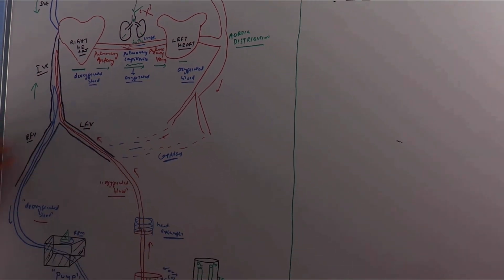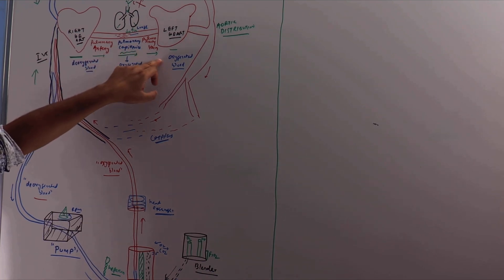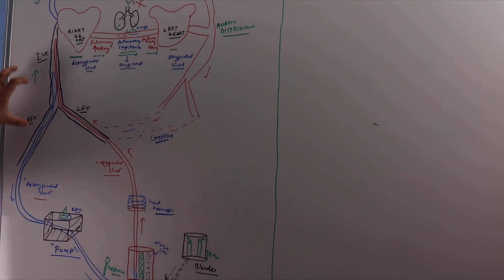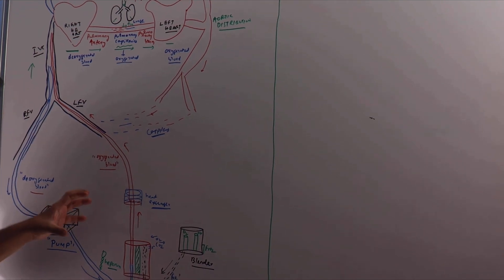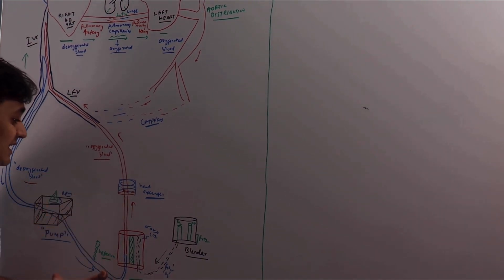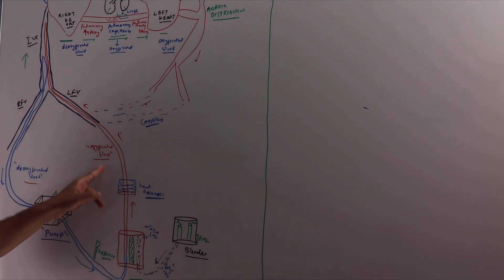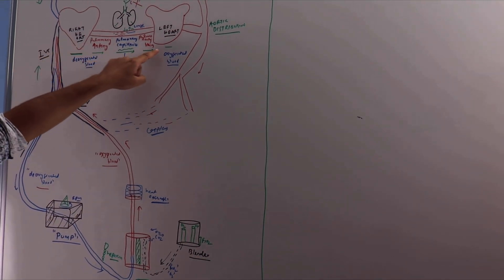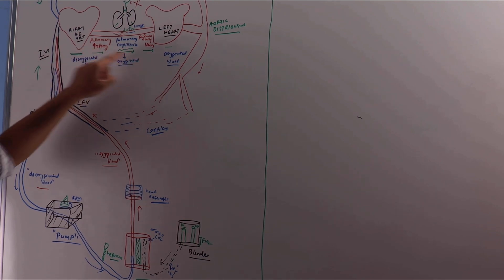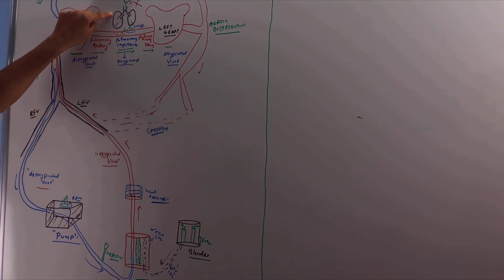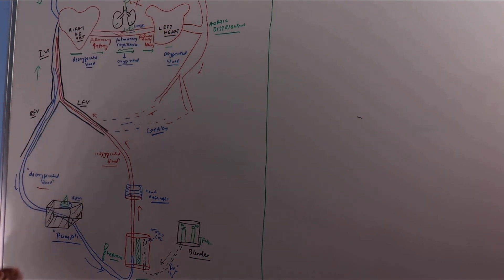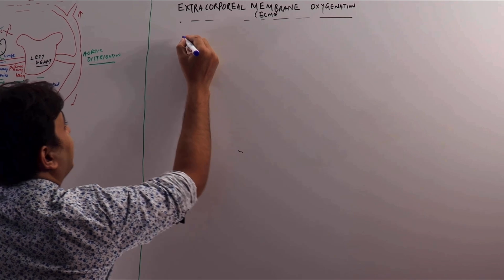Because the left heart is working fine, if we can take out the deoxygenated blood from the body, oxygenate it, and remove the carbon dioxide outside the body using the ECMO machine, then put the oxygenated blood into the right heart — from there it can go to the left heart by the same pathway. Now it is not dependent upon the lungs for gas exchange, so the left heart can distribute oxygenated blood to the whole body. This is the principle of the ECMO machine.